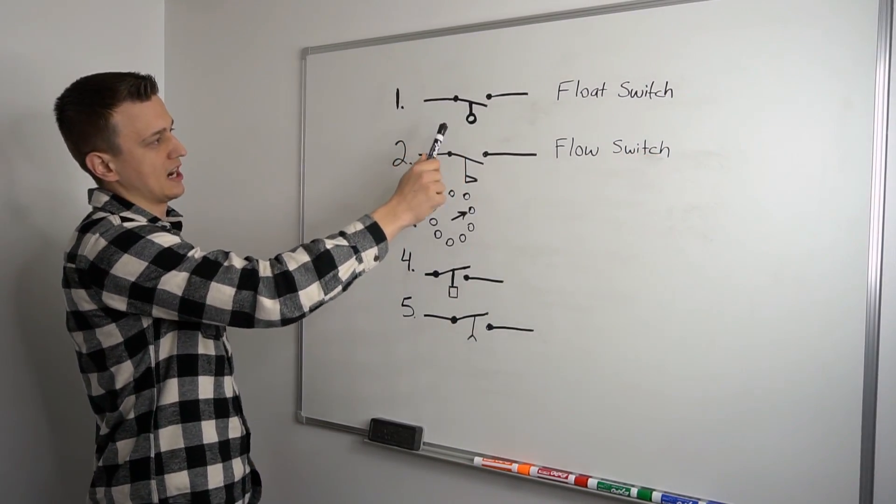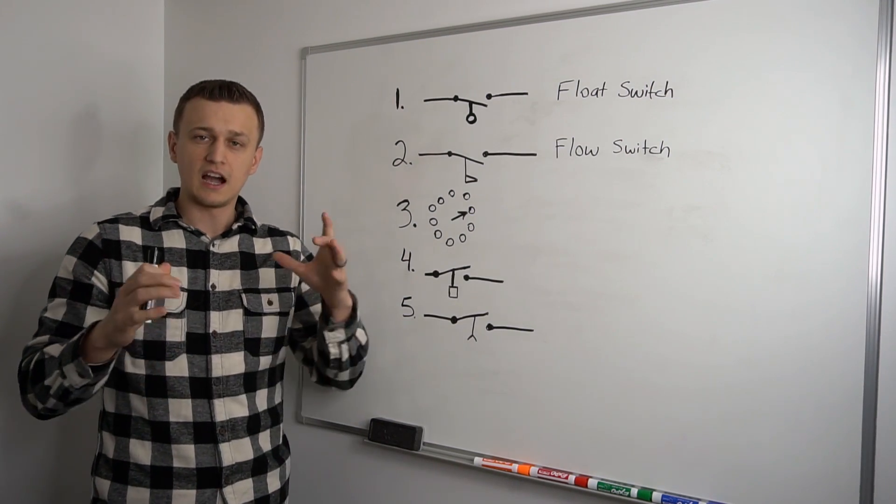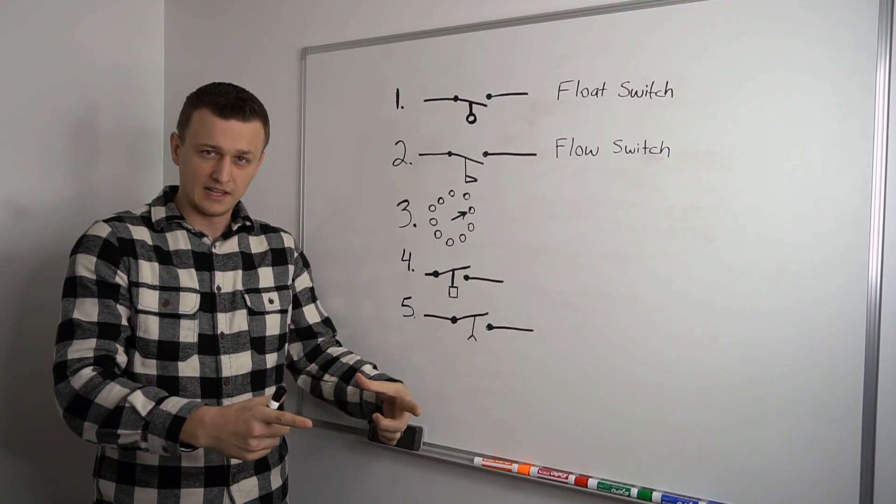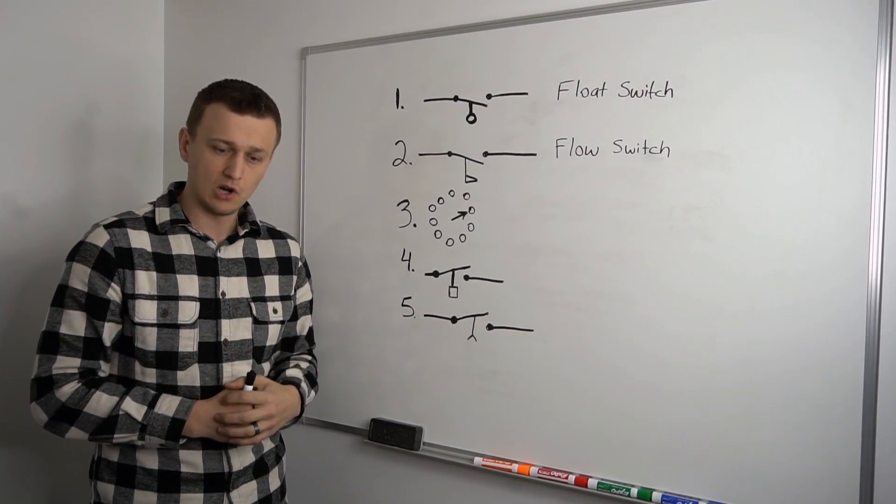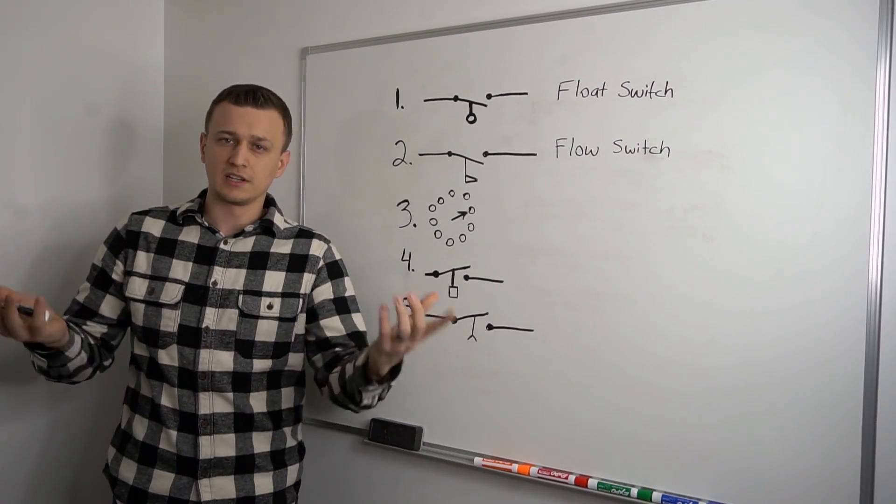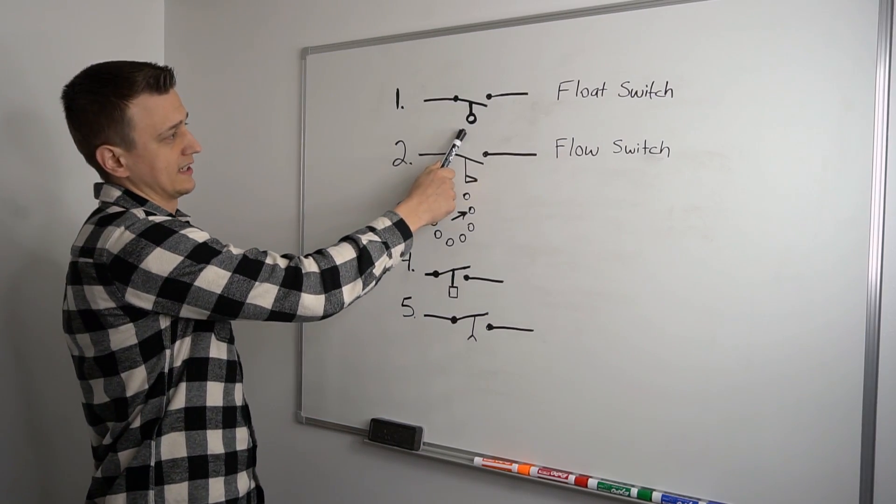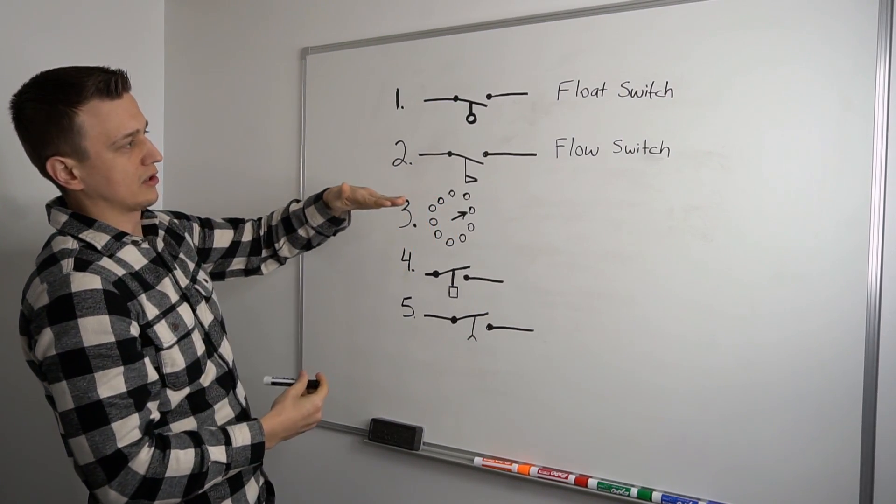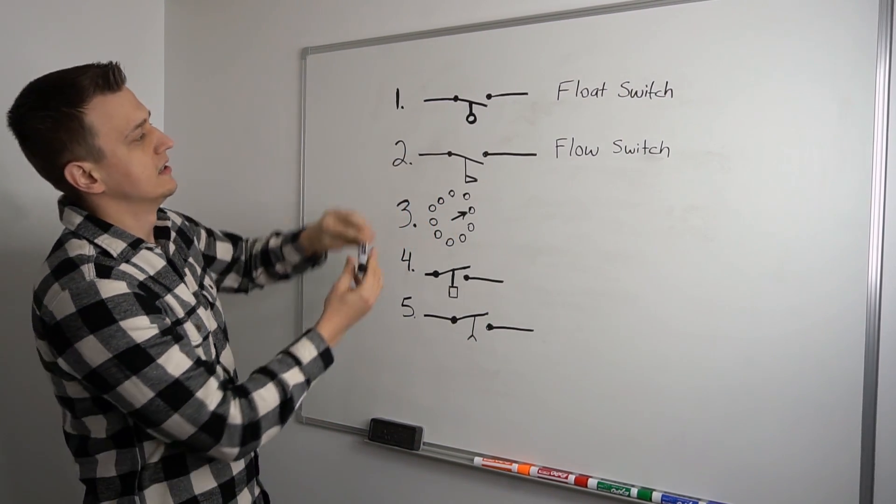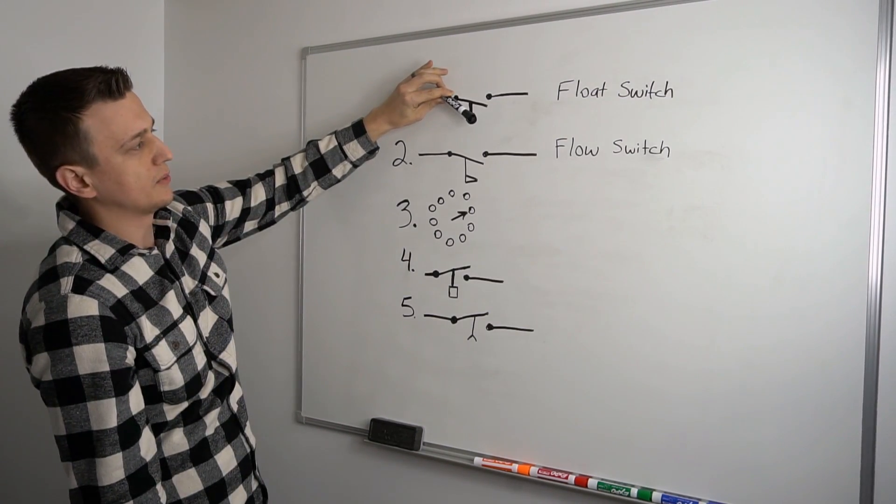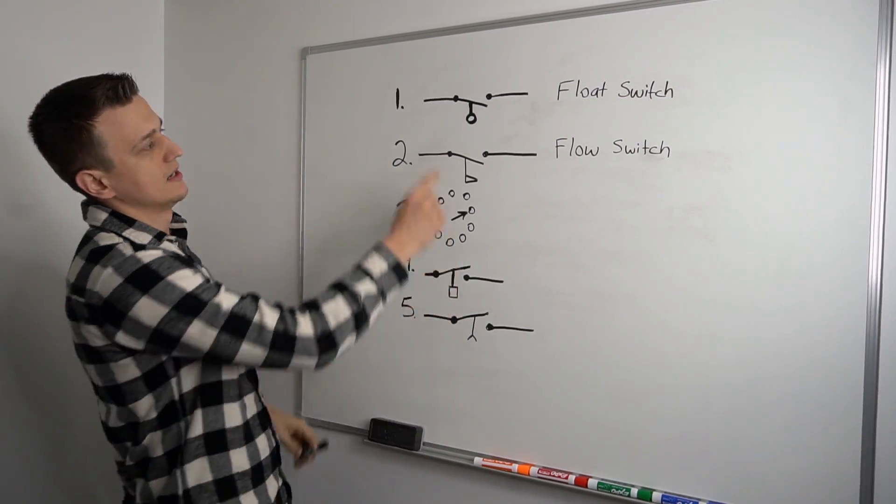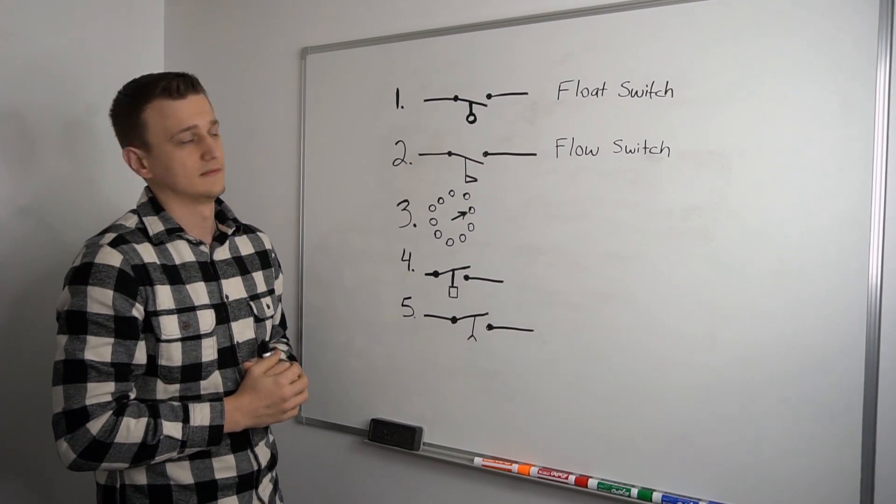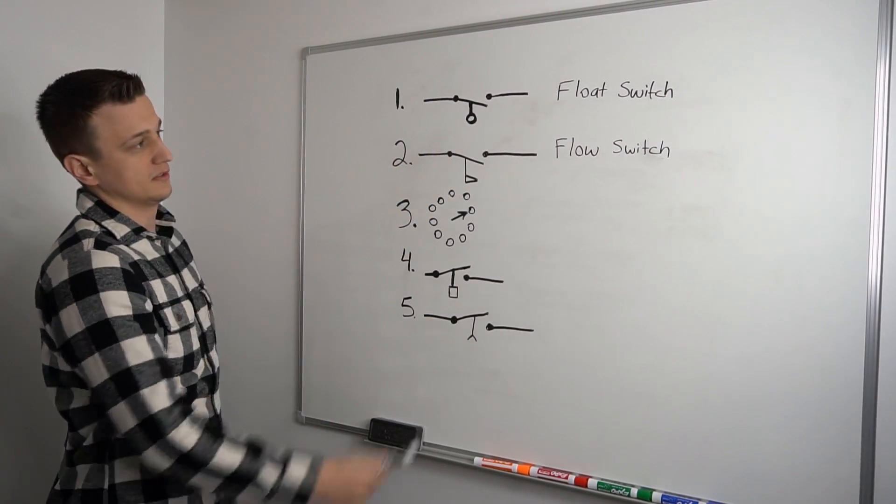So let's start with the float switch up on top. A good example of one of those would be a condensate drain pump on a furnace or maybe for an air conditioner. If the unit does not have a floor drain anywhere nearby, a lot of times a condensate drain pump will be installed to pump out the water to a different location. So one of those things would have a float switch in them. What happens is it has a pan or a collection tank. Water or condensate collects in there. And as the level gets higher and higher, this float switch starts to go up. And when it goes up high enough, it closes and allows power to go through.